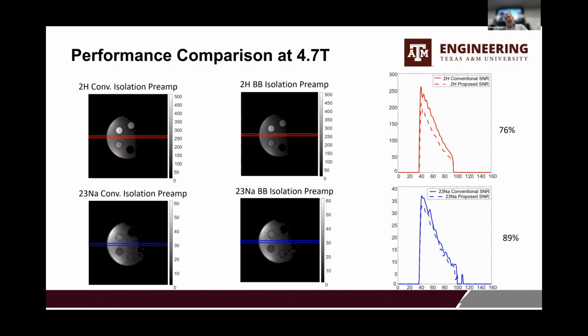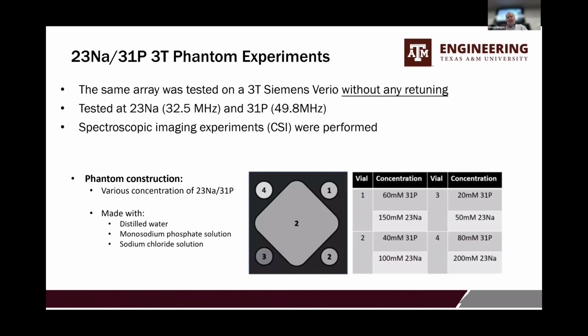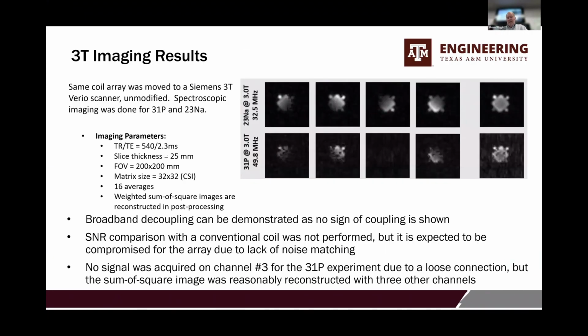So just on a lark, we decided to take the same coil over to a 3T scanner. So a 4.7T coil, we just took it to a 3T scanner, built another phantom with phosphorus, sodium, and proton. And then we stuck it in the same coil and we made images. These were CSI images of sodium and phosphorus on a 3T magnet. Didn't tune the coil at all. We lost one element for some reason. We're not exactly sure what happened.